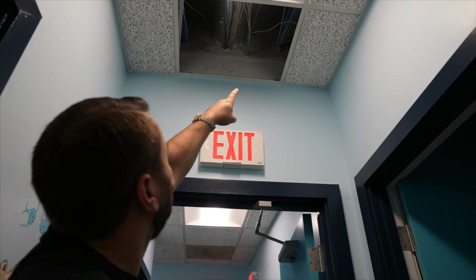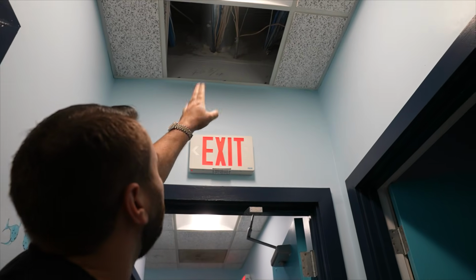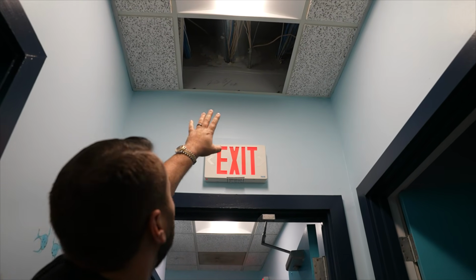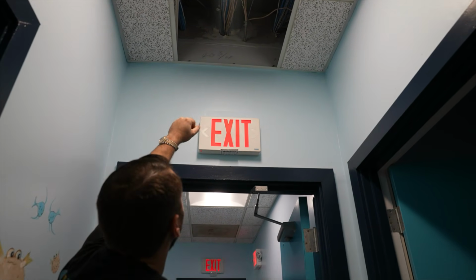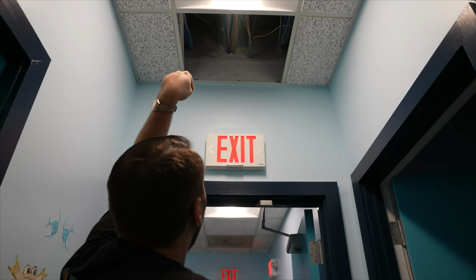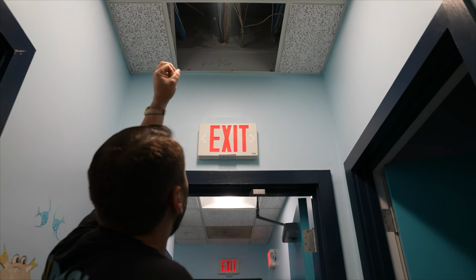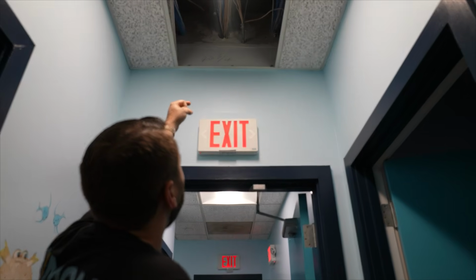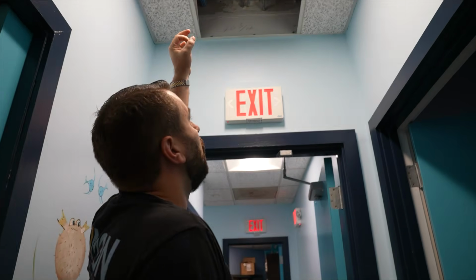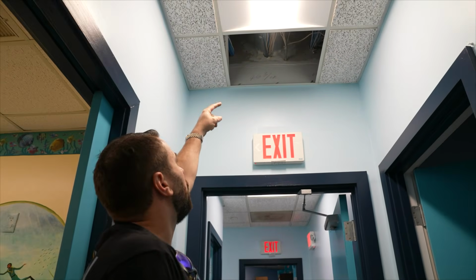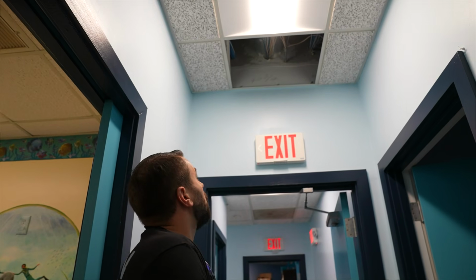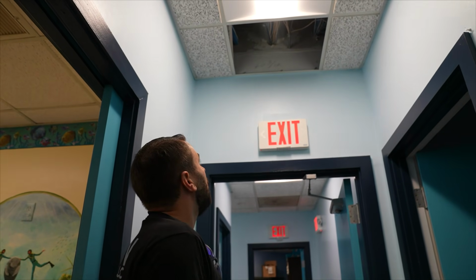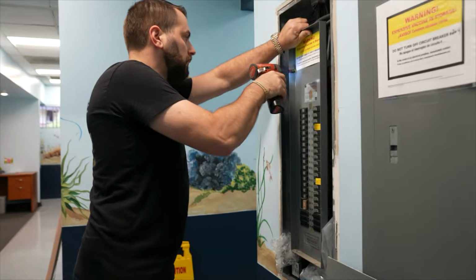There are some other combustible wires that pass through that were done by a different contractor, but we're going to pass our MC cable through a 1/2-inch EMT sleeve, and then we will also foam around it or use fire caulk around it. That way it maintains the integrity of the firewall, and we're following code correctly.